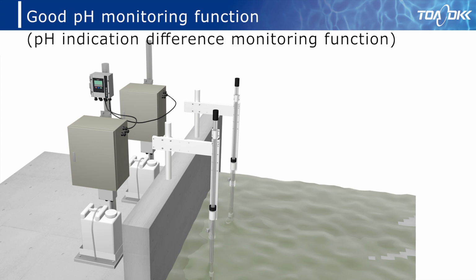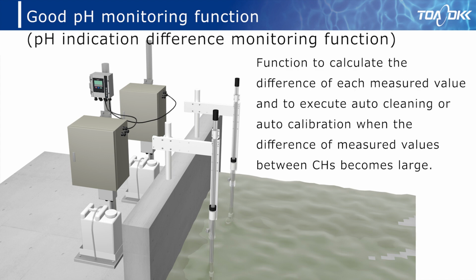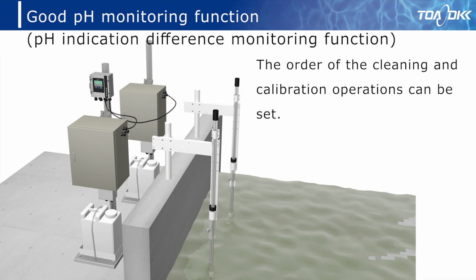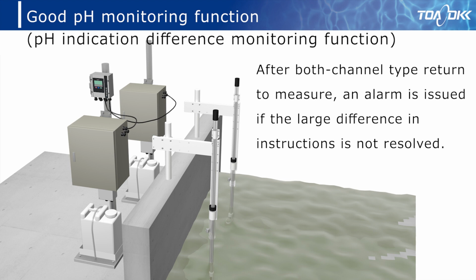We will explain the good pH monitoring function. This is a function to calculate the difference of each measured value and to execute auto-cleaning or auto-calibration when the difference of measured values between parallel CHs becomes large. The order of the cleaning and calibration operations can be set. An alarm is issued if the difference between measured values is still large after both channels return to measurement. In this way, MAC-1600 is able to measure with less missing, thanks to its two-channel measurement.